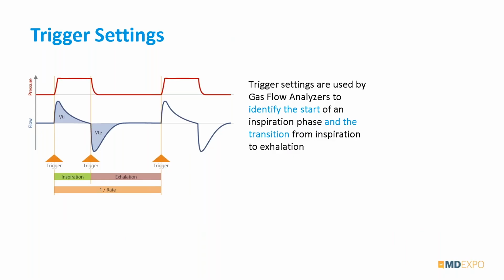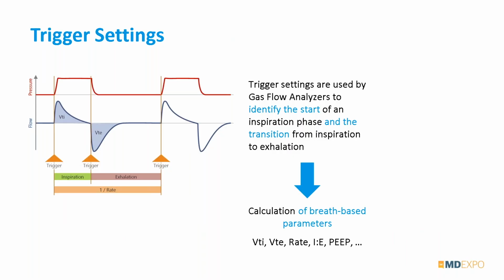So we do that with so-called triggers. At some point the device is going to know, okay, now I start with an inspiration, then it starts calculating all the inspiration parameters, and then at some point it's going to be triggered. Now it changes to exhalation, then it calculates values from there, and then with the next inspiration it starts over again, because this can depend on settings on the ventilator. And this is important for many different parameters, I don't know, 20 plus, that you can see on typical gas flow analyzers, all based on these trigger settings. So if your gas flow analyzer doesn't trigger, then you can't measure these parameters at all, okay?